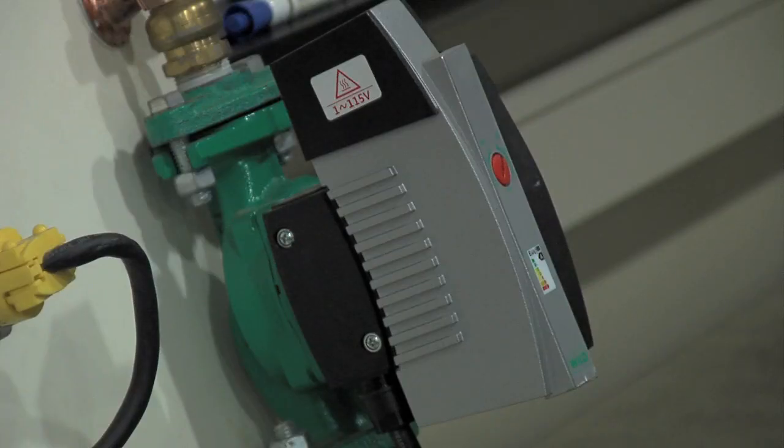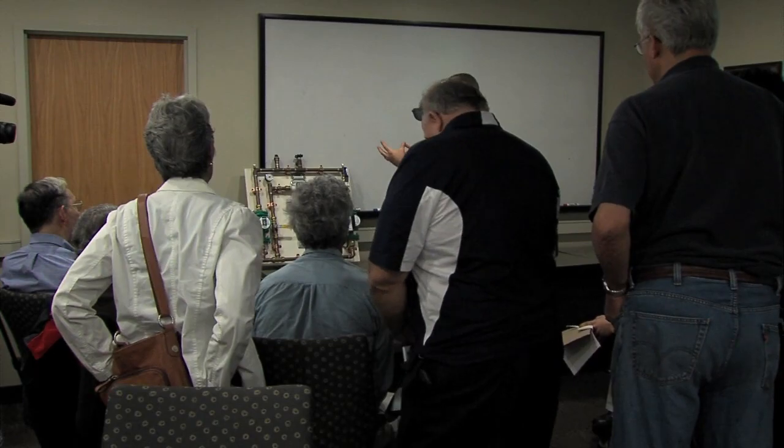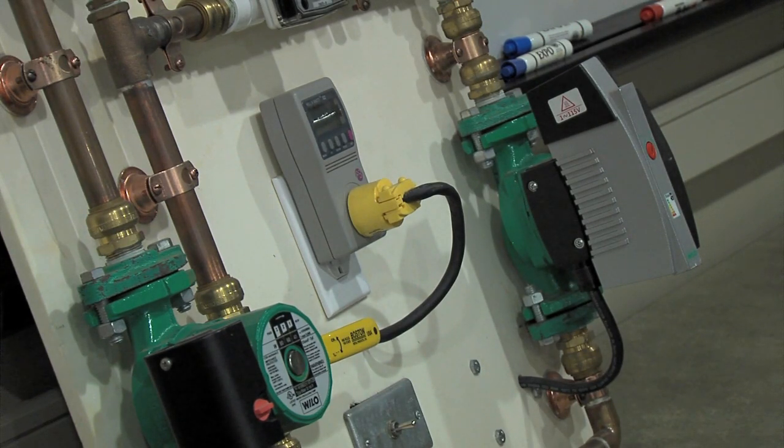When you get into the commercial pumps, you're 220 volts, 208, 230 volt range, and you go from about 20 gallons a minute to 200 gallons a minute is the range on the single pumps. And they're very clever. They've taken a volute, which houses the pump, and they've made them into a double volute, single flanges, 2 pumps. And so now you effectively have double the flow, same head, same head it can overcome. So now you've got 400 gallon a minute pumps that don't require any of the hardware.